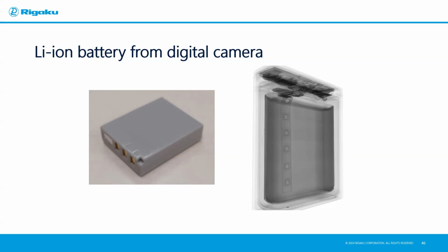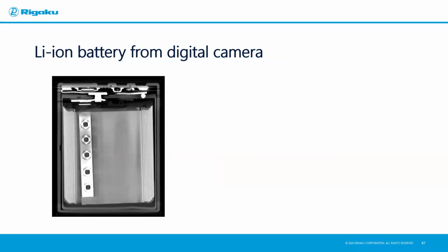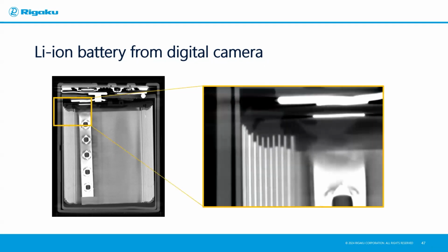One of the things that battery manufacturers are generally doing is looking at this layering and the anode overhang, and many programs can characterize the properties of the anode overhang to see if it's bent, if it's curled, and so on. But there are some other things that could also be important that you can see in this case. So if we take a cut straight through vertically, this is a 2D cross section, and we can see these layers. And like I said, this is an important part to characterize.